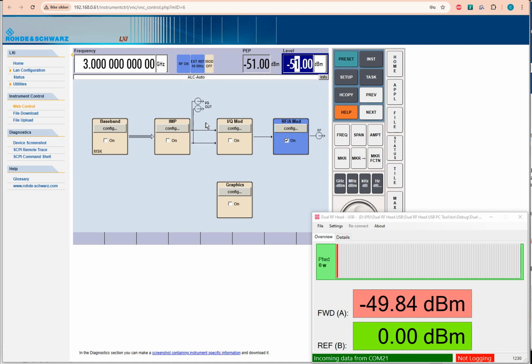And if we continue and if we get more than 10 dBm below the minimum calibration point, which was -40, it will tell you, sorry, can't calculate because you're outside the calibrated range with more than 10 dB. So let's go up and we can just type in here 0 dBm, and we can go up 2 dB. Now you will soon see a small slight roll off to 0.6 here, 1 dB, 1.4, 1.7. So this is the practical limit, around -50 to 0 dBm. That's where you have the highest accuracy.